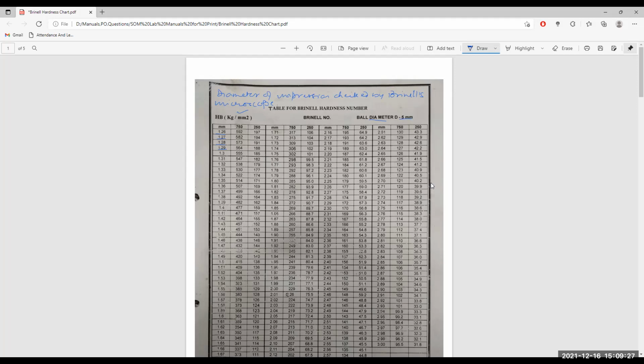Now, what is shown here? There are certain other items like 750, 250, 750, 250. These are the amount of load applied to the ball, the load placed on the hanger to be applied to the ball. So with a 5 millimeter ball and by applying a 250 kg weight, if you get an impression of 1.26, which is the minimum impression, just more than 1 millimeter, the hardness should be equal to 196. That is the minimum hardness we can take on this type of machine.